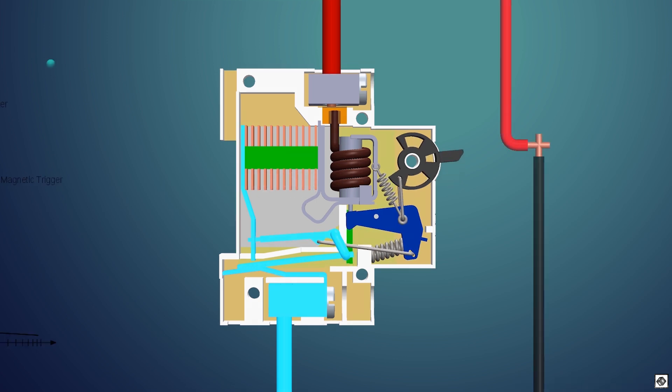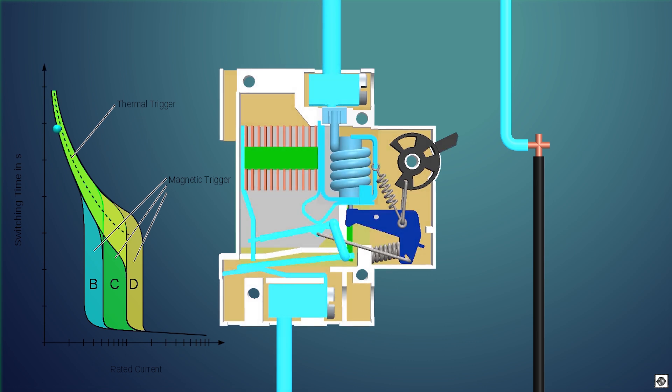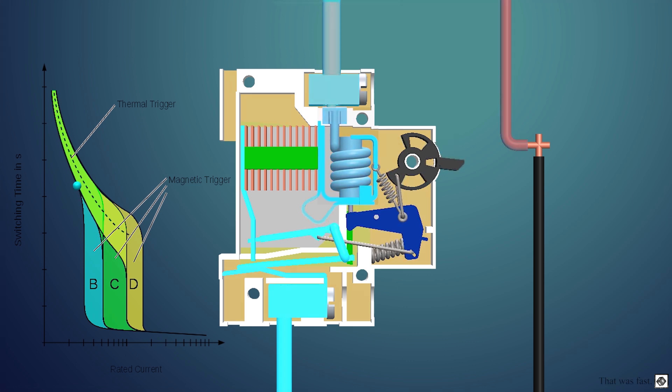Now, let's see the short circuit situation. In a short circuit, a large amount of current flows through the MCB. As the current flows through the solenoid, it creates a strong magnetic field. This magnetic field pushes the pin placed in the solenoid.